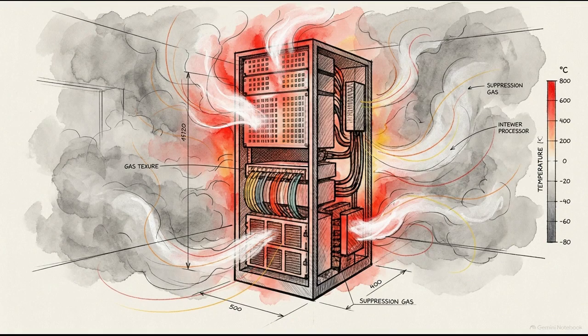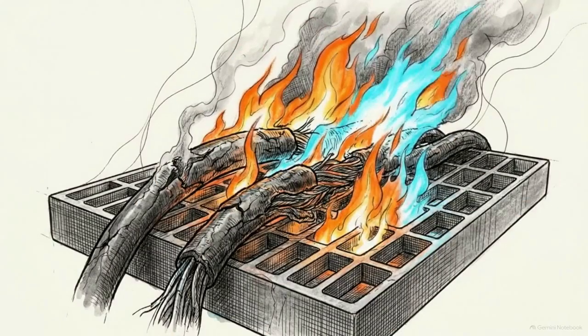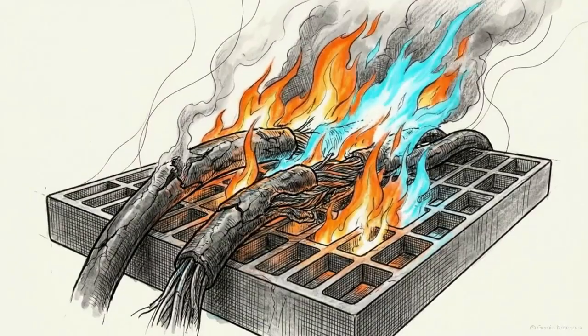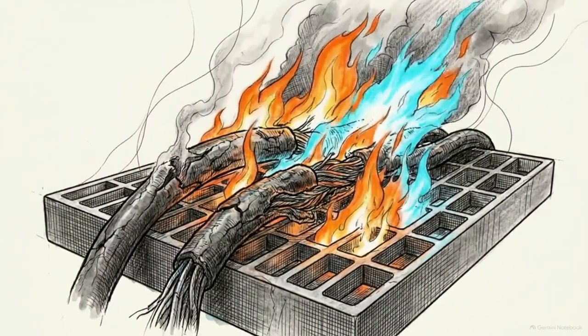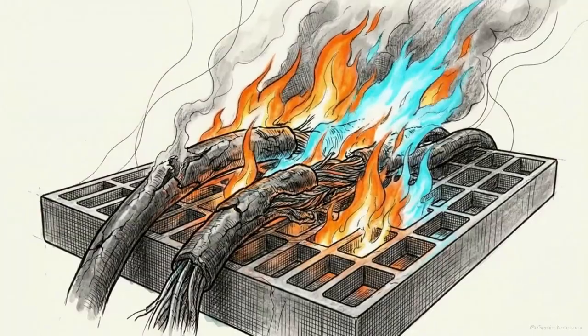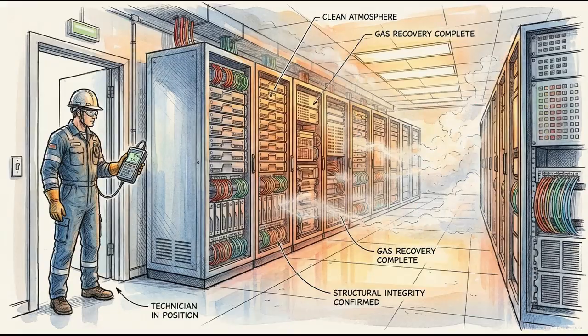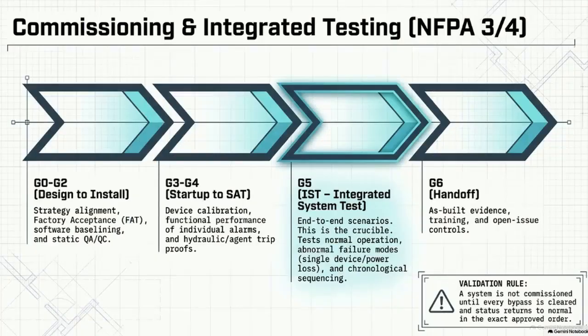Even with a perfect enclosure, these agents offer minimal thermal cooling. Deep-seated, energized thermal faults will immediately reignite once the agent dissipates. Gas discharge alone is an incomplete protection strategy. Once the fire is out, the post-event recovery phase, safe isolation and atmospheric purging, relies on the system acting exactly as it was originally commissioned. Proving that design reality requires following the NFPA 3 and 4 commissioning sequence, culminating in G5, the Integrated System Test.